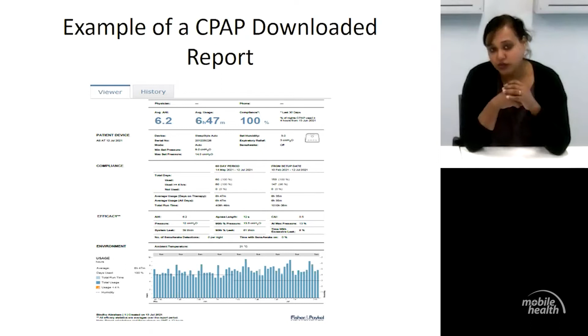So I've got a picture or an example of a download up there for you. If you look at this report, it basically tells us the pressure setting for this patient. So they've got a minimum set pressure and a maximum set pressure. It tells us what type of machine it is. It tells us the humidity, which is how hot or how cold the air is that's coming out for the patient. And there's a comfort setting, which the patients usually self-adjust themselves using the buttons on their machine, but at least we can see what the setting is. So if they were to ring us with problems, we can usually look at the report and troubleshoot from the report itself. It gives us an average usage.